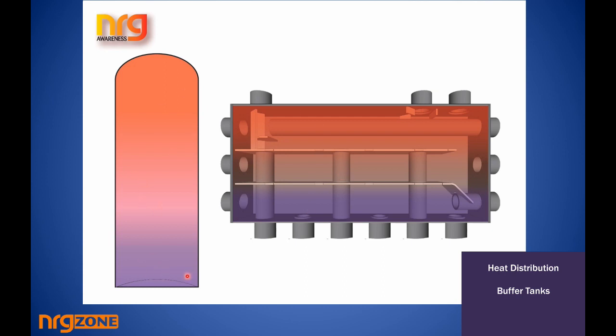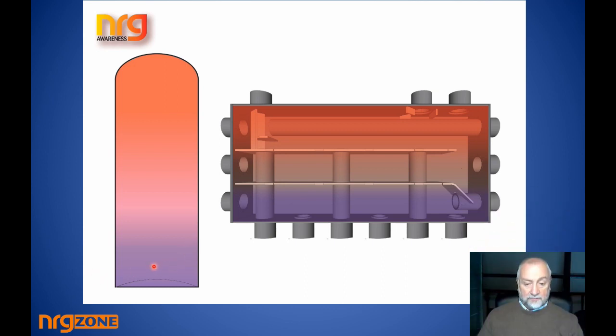If you have a connection at the bottom and that connection is connected to the boiler or heat appliance, then the coldest water that's lodged at the end of the buffer, because of stratification, will be drawn back into the appliance, and therefore you have a very good chance of having proper efficiencies in the system. But if you think about it, in one breath a manufacturer could say that you need the stratification for their boiler to work with a buffer, and then the same manufacturer might be selling a low loss header, which contradicts the whole point of what we're talking about.